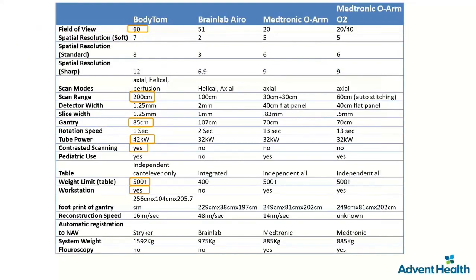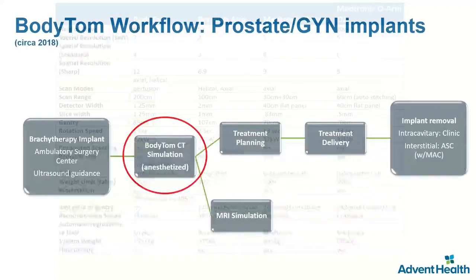When we did our initial evaluation of the CT scanners out there, how we landed on the BodyTom is highlighted here. It has a very large field of view, which is important, especially here in Central Florida, as we do have some larger patients where that would be an issue. It definitely had the largest scan range of anything available. It's a large bore; the gantry is 85 centimeters. It had the strongest tube power on the market. It had the ability to do contrasted scans. The tables that were available could handle over 500 pounds and had an independent workstation.